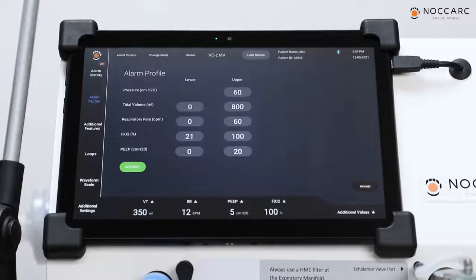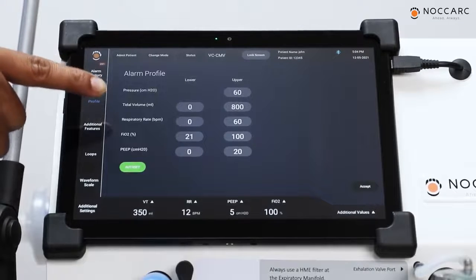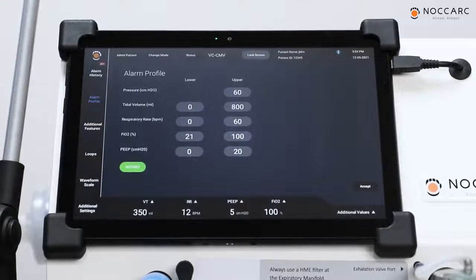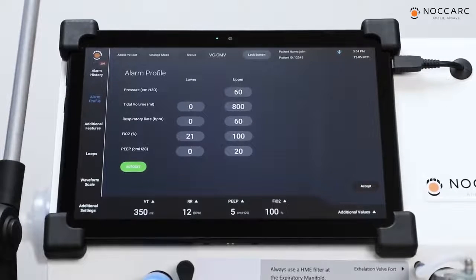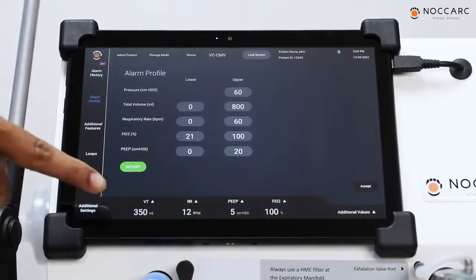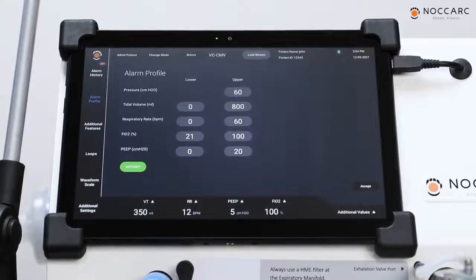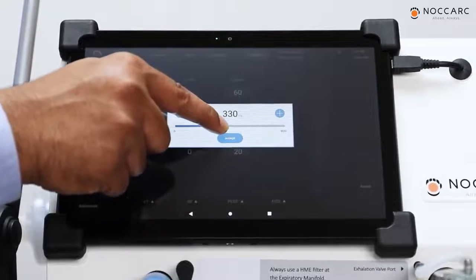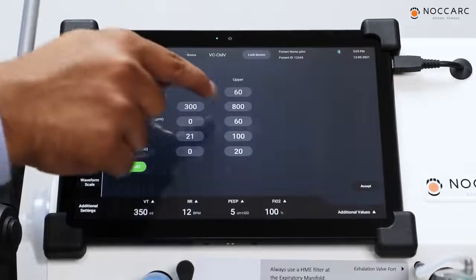The user can also change the alarm values when the patient is being ventilated by tapping on the alarm profile button. In the alarm profile window, the lower limits and upper limits are provided for parameters such as pressure, tidal volume, respiratory rate, FiO2 and PEEP. Here we have to set the limits as per the set values. We have set tidal volume 350. So I will set the lower limit for tidal volume 50 ml less than the set value, that is 300 ml, and the upper value 50 ml more than the set value.